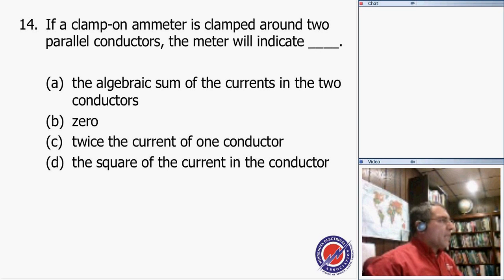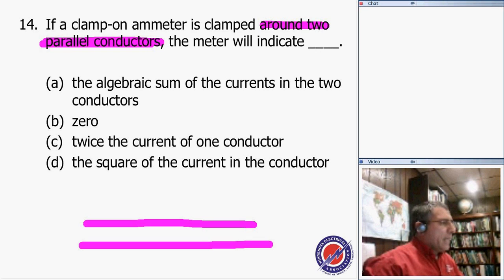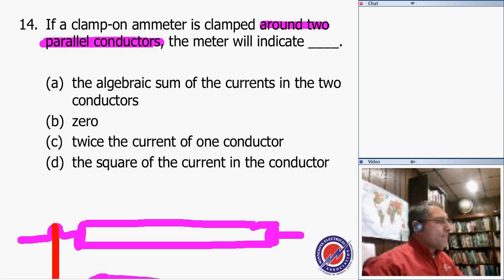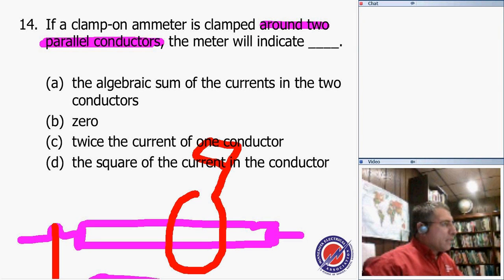Number 14: a clamp-on ammeter is clamped around two conductors. This is really interesting because some of you got number 14 wrong. I want to emphasize the word parallel conductor. Here's an example, guys. We have phase A, tied at both ends and tied to a circuit breaker. Phase B is the same, tied together at the end and tied to another circuit breaker. And phase C is going to be tied to the second circuit breaker. In reality these two circuit breakers are one circuit breaker. So if you bring the clamp-on ammeter and clamp it across the two conductors, this is phase A, this is phase B, and this is phase C.